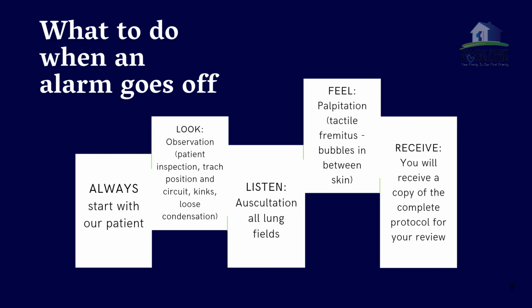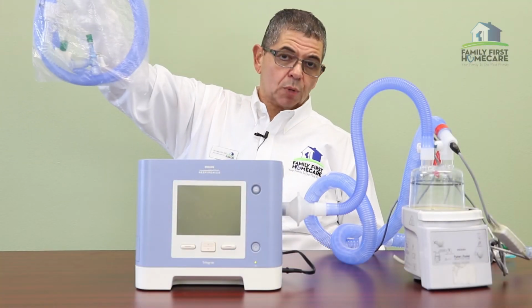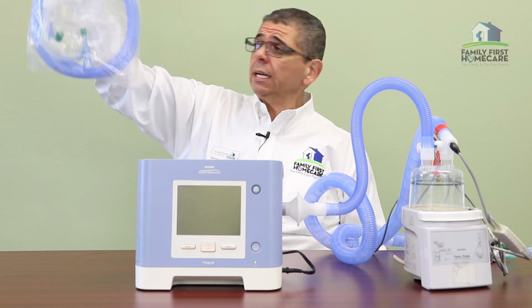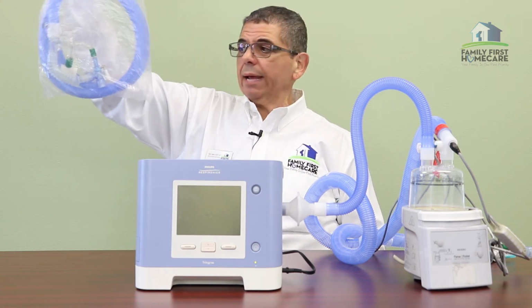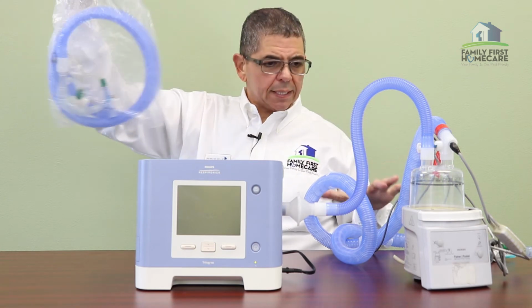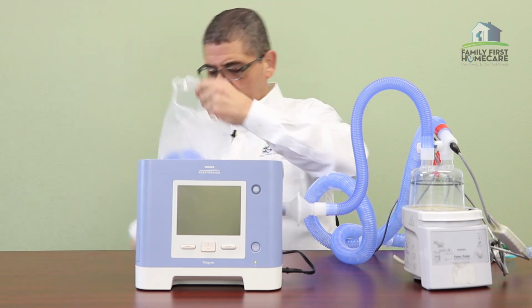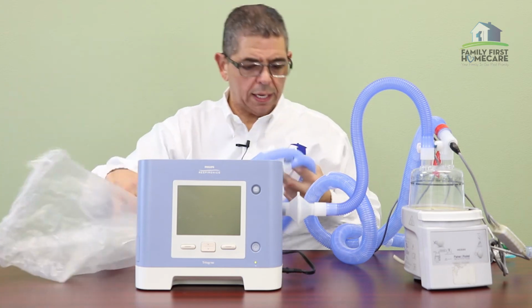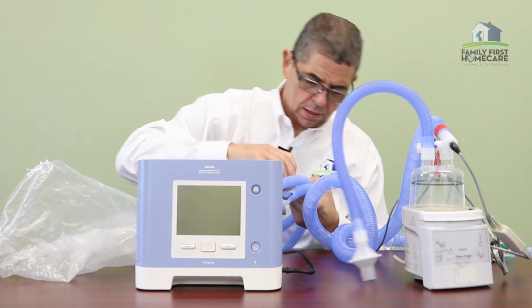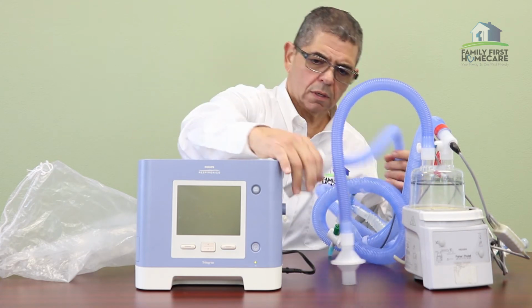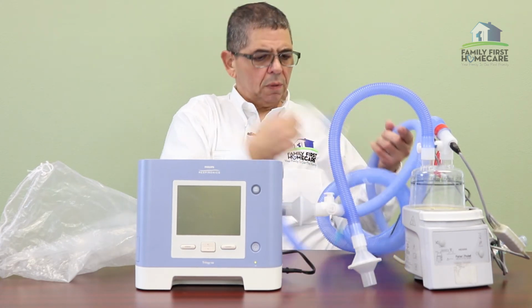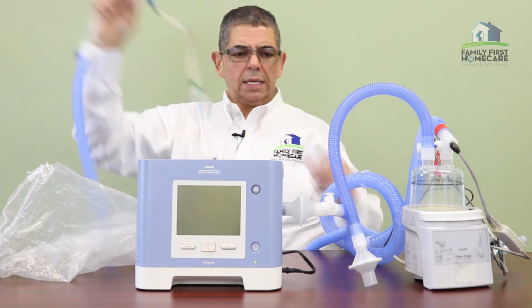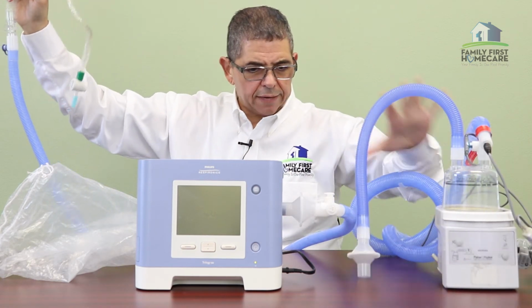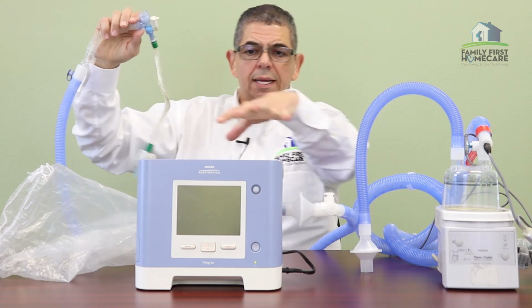If the patient is completely fine, the chances are the issue is going to be in the circuit. So what we have prepared is basically an emergency circuit. This will be hanging by the side of your bed, and since we know the problem might be in here, we're going to try to eliminate that problem pretty quickly, because we have one that is ready to roll. We can simply disconnect that from here, go right over here with a whole fresh new system, and we're ready to go. We can now eliminate any of the problems that might have occurred inside of here. And now if it's still alarming, it's the machine.